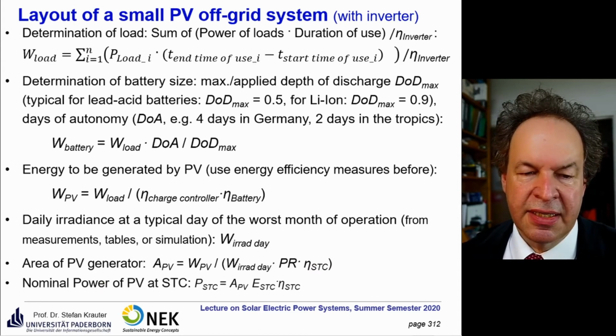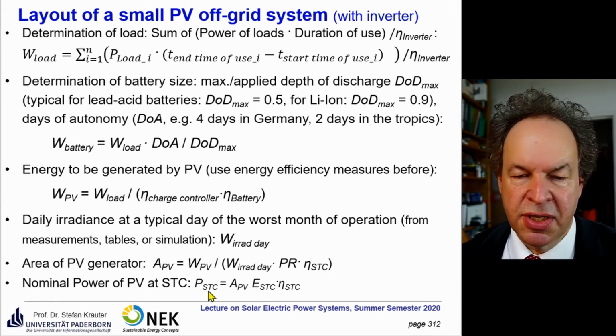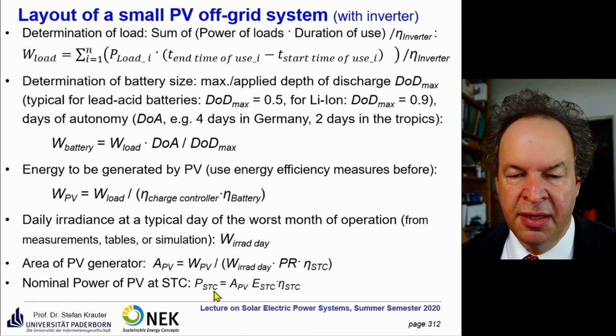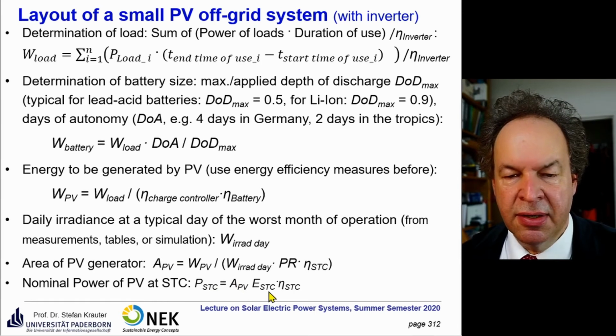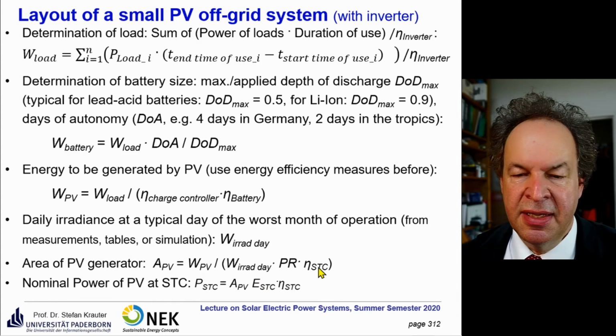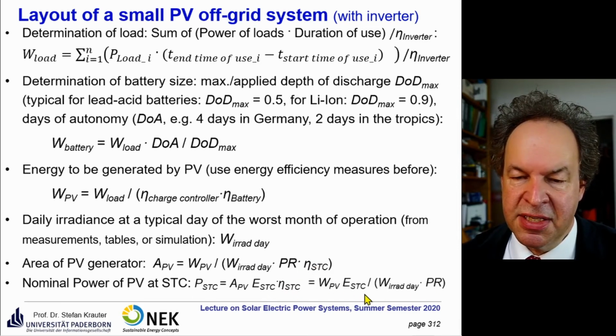You can also calculate not only the area, but the nominal power of your PV generator. This is P under STC, expressed in watt peak. You have the area times E, the irradiance under standard test conditions, which is 1000 watt per square meter, and the efficiency under standard test conditions. You see this term appears on both the lower and upper part, so it gets eliminated, making the expression a bit easier.